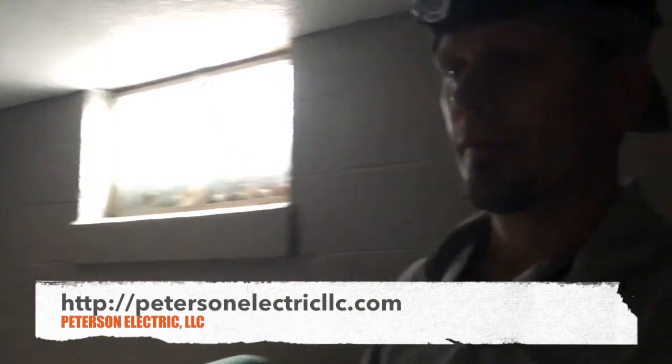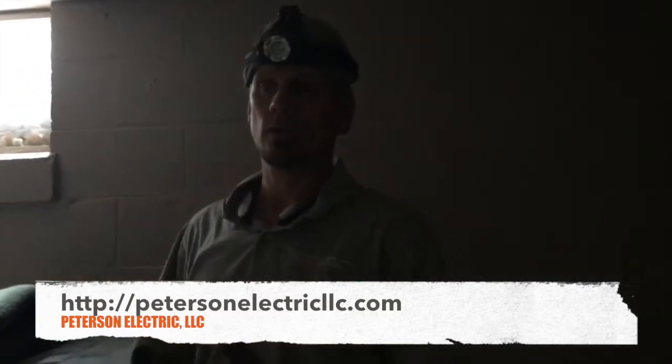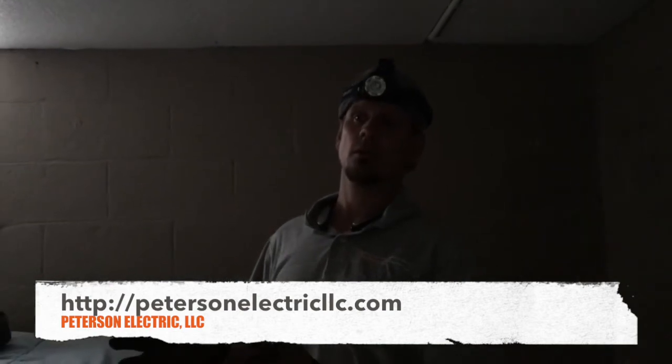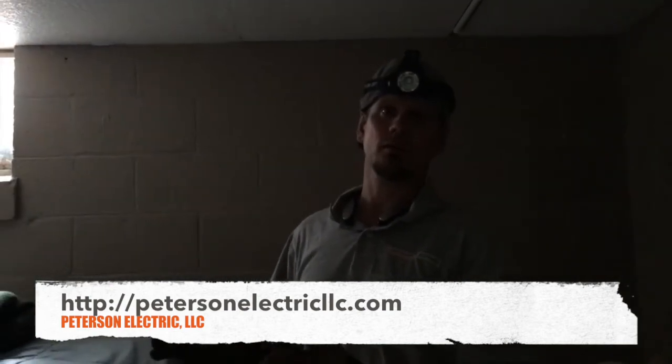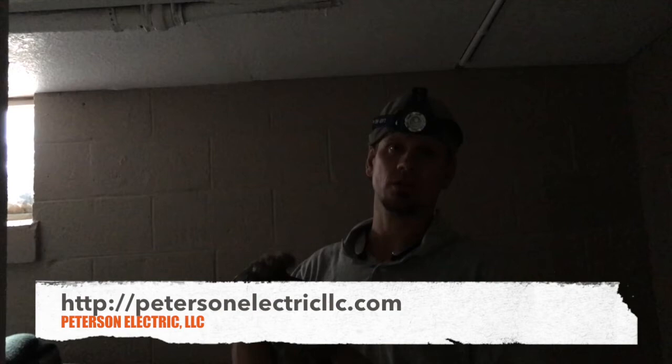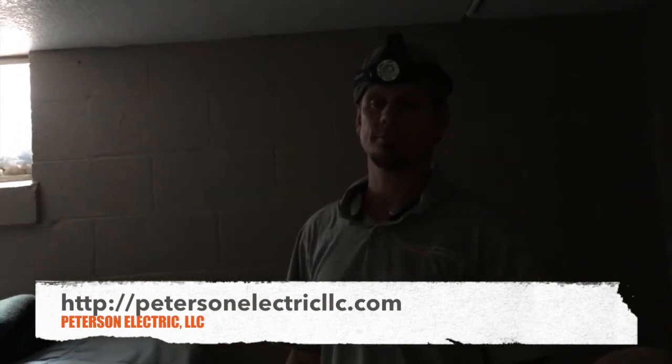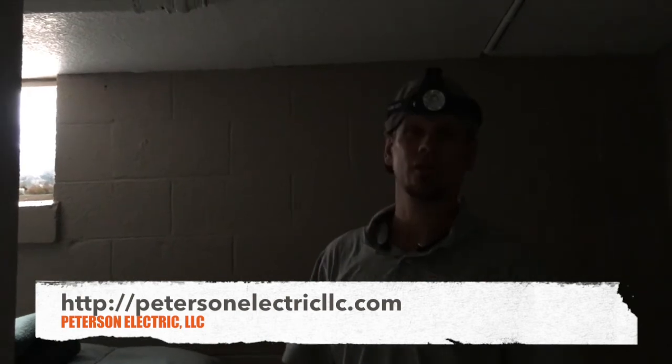So the cutoff is that she doesn't have to do all her branch circuits as long as she doesn't move that panel more than 6 foot. So we technically need to leave that panel, get the plumbing fixed, put a shield, change that out, do the service, and redo it all. This is going to be a very expensive service change.